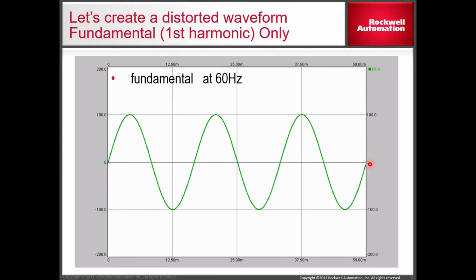So let's go back and look at the fundamental frequency of 60 Hertz. When we introduce nonlinear loads, we impose other harmonics or frequencies on top of this fundamental one. Now, the rules are that even harmonics, like the second, fourth, sixth, etc., don't contribute to this, nor does any harmonic that is divisible by 3. So 3, 6, 9. So what's that leave us with? The first harmonic we need to be concerned with is the fifth harmonic.